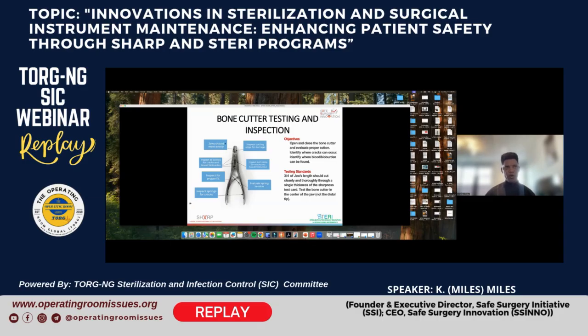The same thing with a bone cutter. You have very similar inspection points. As you can see in this picture, this bone cutter actually is missing a screw, and the springs are not aligned. So I put this in as an example to show how an instrument could look in your facility if you're not going through the inspection process. Again, you're going to go through looking at springs, inspecting the springs for fit, checking for cracks, just like you would with the rongeur.